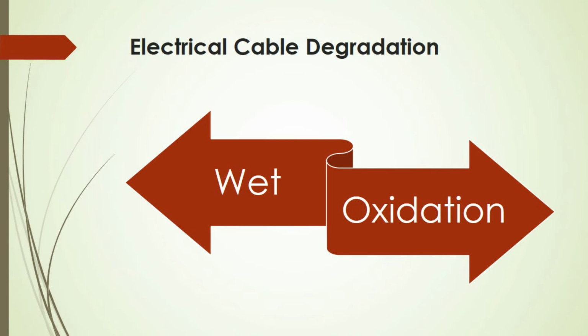The production of radical species initiates and maintains oxidation in polymers. And due to thermal vibration or high-energy photons, chain scissions produces free radicals, which subsequently combine with oxygen to form high-energy activated moieties. The auto-oxidation process is then repeated when these radicals react with another molecule to reduce their energy state. The use of antioxidants in dielectrics, such as bulky phenols or hindered amines, is known to reduce auto-oxidation by consuming these free radicals as they are being created.